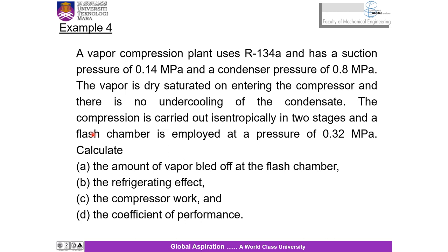This is different compared to our earlier example. Our earlier example employed a heat exchanger for the cascade refrigeration system, and in this example we are using a flash chamber, at a pressure of 0.32 megapascal. You are asked to calculate, for part A, the amount of vapor bled off at the flash chamber.